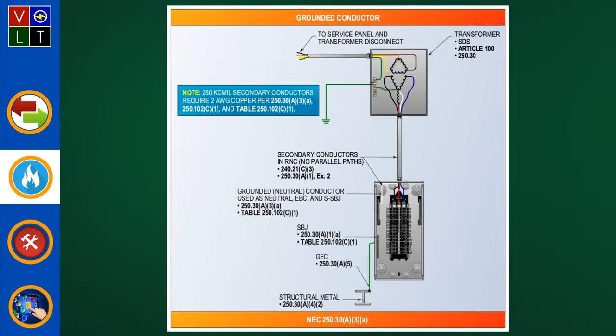When I'm looking at parallel conductors in 2 or more raceways, it tells you here that the grounded neutral conductor shall be based on the total circular mil of the ungrounded phase conductors when installed in parallel, which of course is in 2 or more raceways. The grounded neutral conductors installed in those raceways shall be based on the size of the ungrounded phase conductors in the raceways, but since it's in parallel, it shall not be smaller than what?